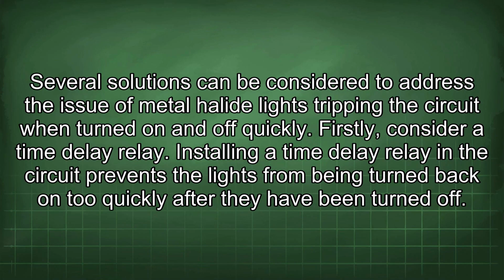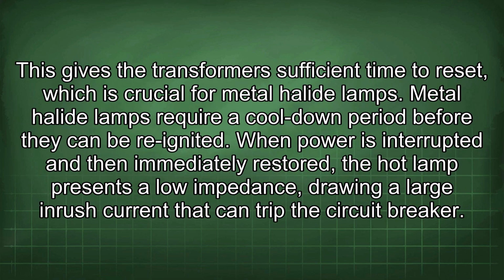Several solutions can be considered to address the issue of metal halide lights tripping the circuit when turned on and off quickly. Firstly, consider a time delay relay. Installing a time delay relay in the circuit prevents the lights from being turned back on too quickly after they have been turned off. This gives the transformers sufficient time to reset, which is crucial for metal halide lamps. Metal halide lamps require a cool-down period before they can be reignited.